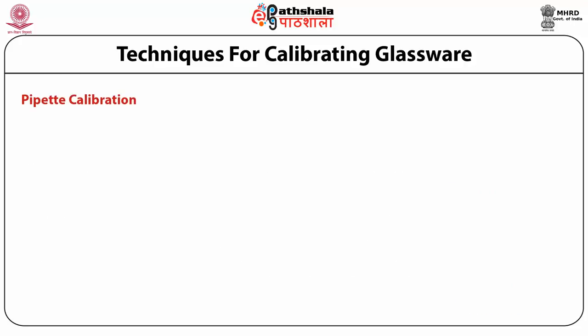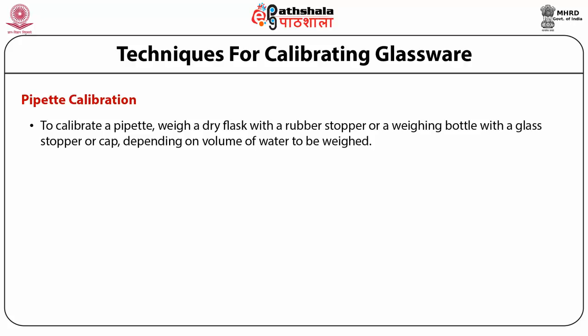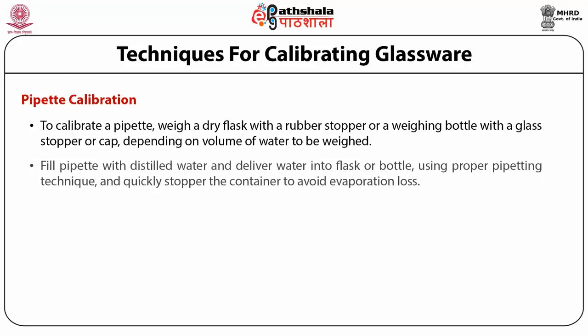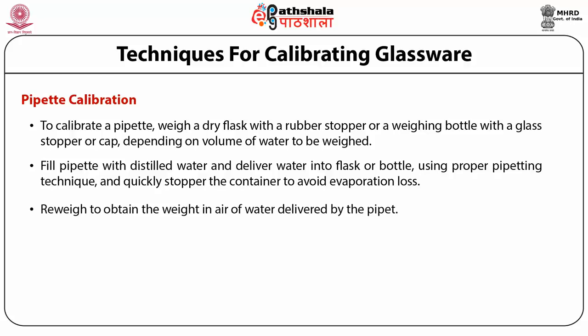For pipette calibration, weigh a dry flask with a rubber stopper, or a weighing bottle with a glass stopper or cap, depending on the volume of water to be weighed. Fill the pipette with distilled water and deliver the water into the flask or bottle using proper pipette technique, then quickly stopper the container to avoid evaporation loss. Reweigh to obtain the weight in air of water delivered by the pipette.